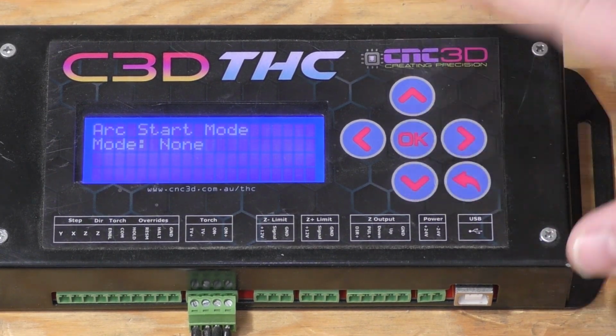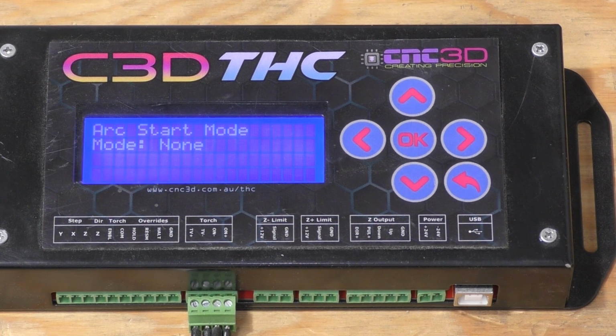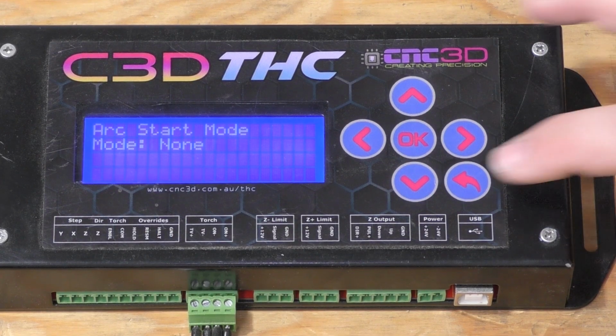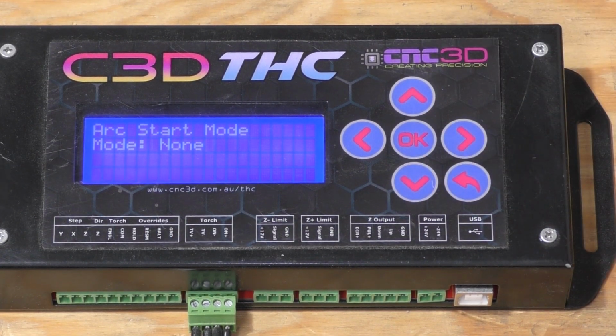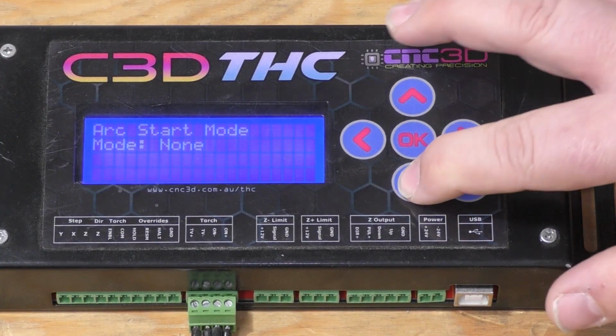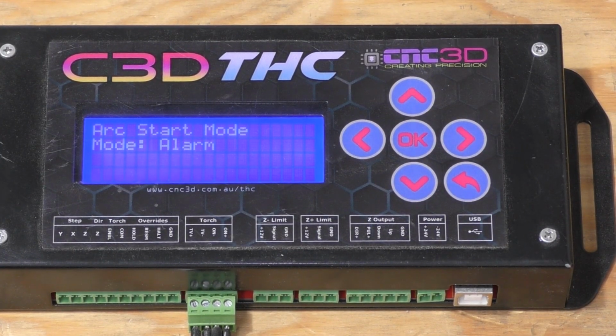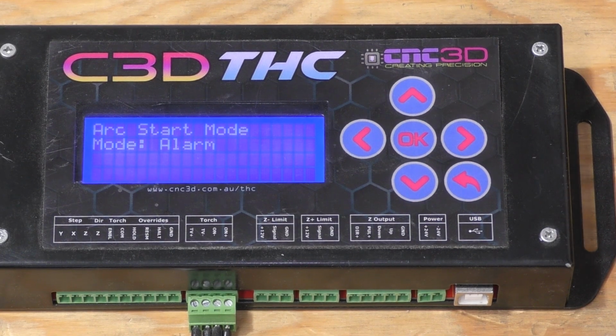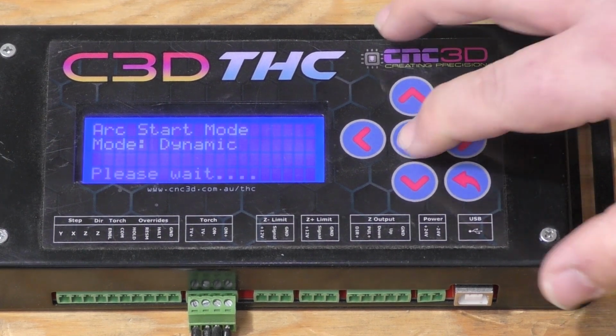In none mode, all it will do is ignite the arc and it will not look for an arc OK signal. It will just continue going regardless of what the arc does. This is the mode you will use if your plasma cutter does not have an arc OK signal output. In alarm mode, if it detects that the arc has ignited and you've got an arc OK signal, it will just continue the job as per normal. If the arc ignites but there is no arc OK signal, there is no good arc, it will send an abort or an e-stop to the controller to stop the job.